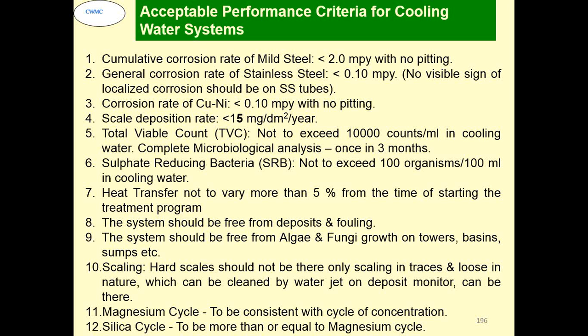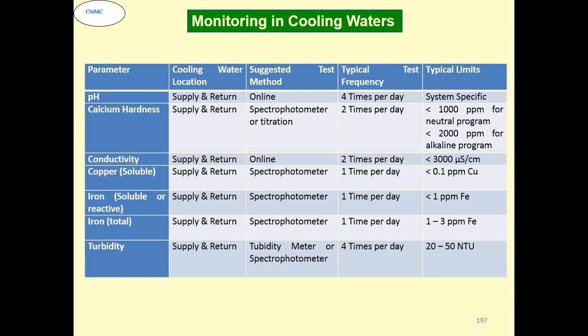Heat transfer not to vary more than 5% from the time of starting the treatment program. System should be free from deposits and fouling. System should be free from algae and fungi growth on towers, basins, sumps, etc. Scaling: hard scale should not be there. Only scaling that is loose in nature, which can be cleaned by water jet on the deposit monitor, can be tolerated. Magnesium cycle to be consistent with cycle of concentration. Silica cycle to be more than or equal to magnesium cycle.